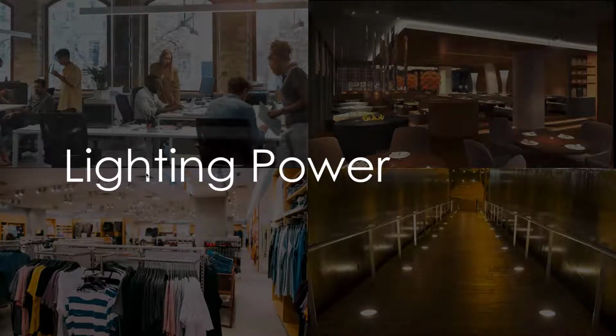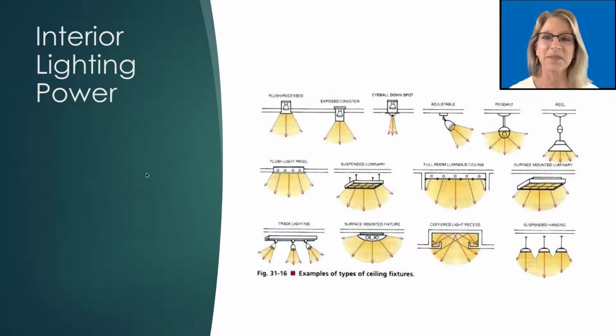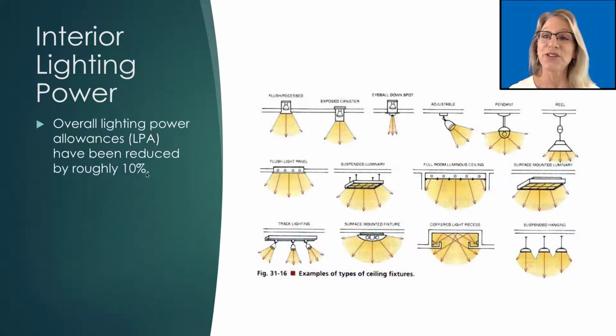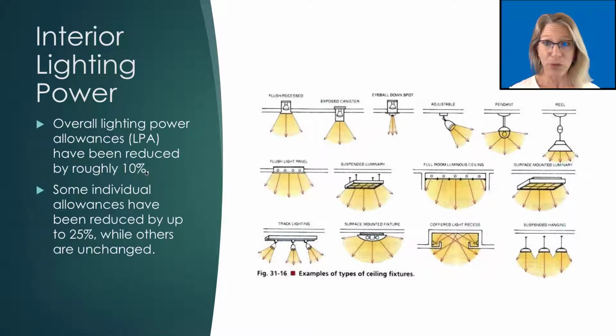Let's start with lighting power. During the code change proposal evaluation process by the State Building Code Council Energy Code Technical Advisory Group, the TAG reviewed 3 different options that had been submitted for the lighting power allowance reduction. Multiple industry representatives and code development experts were involved in this debate. The updates that were eventually selected reflect roughly a 10% reduction in lighting power allowance values. This is not an across-the-board reduction.